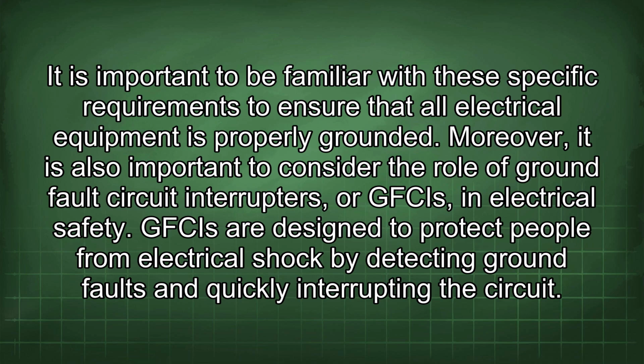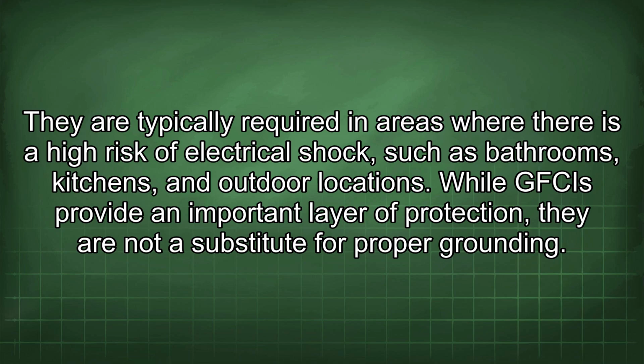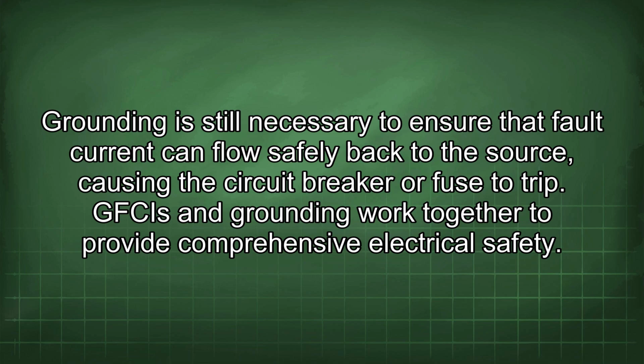is properly grounded. Moreover, it is also important to consider the role of ground fault circuit interrupters, or GFCIs, in electrical safety. GFCIs are designed to protect people from electrical shock by detecting ground faults and quickly interrupting the circuit. They are typically required in areas where there is a high risk of electrical shock, such as bathrooms, kitchens, and outdoor locations. While GFCIs provide an important layer of protection, they are not a substitute for proper grounding. Grounding is still necessary to ensure that fault current can flow safely back to the source, causing the circuit breaker or fuse to trip. GFCIs and grounding work together to provide comprehensive electrical safety.